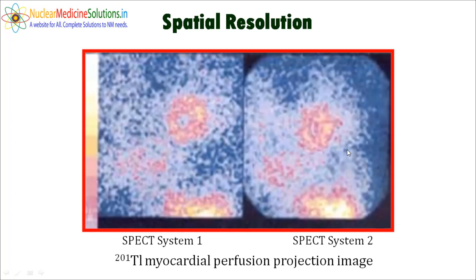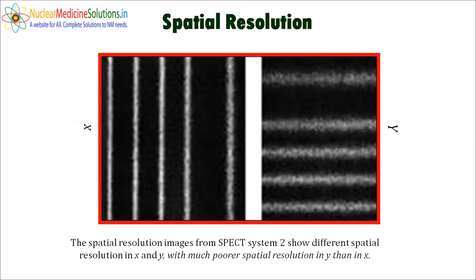So how the spatial resolution affects your image can be understood by seeing this example. This is a cardiac perfusion study performed on SPECT system 1 and SPECT system 2. SPECT system 2 is showing a bad resolution of the image compared to SPECT 1. When we perform a resolution test of SPECT 2, we find that the resolution in the Y direction is not good, and due to that we are getting a bad resolution. So always perform the resolution test in both X and Y direction.